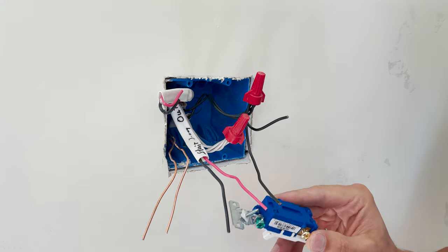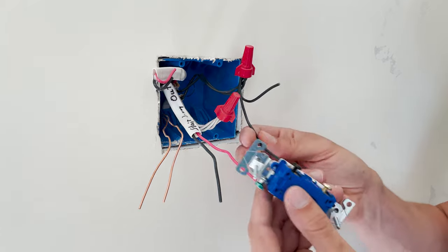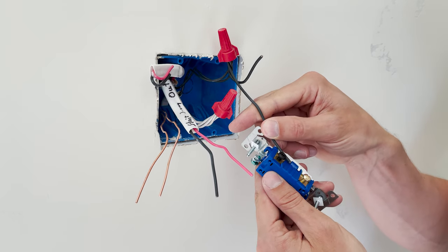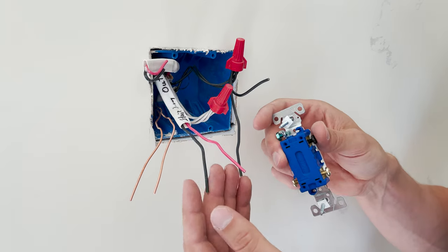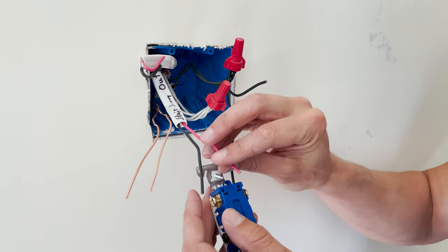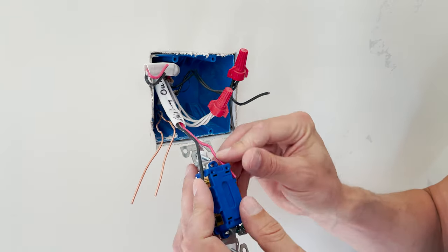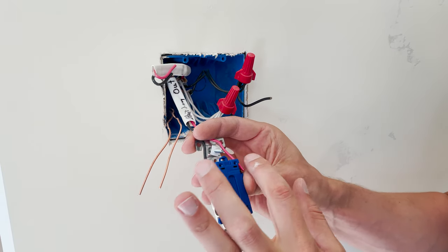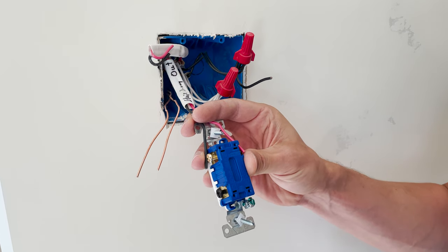So on this, we are going to ignore this kitchen one because we're not worried about that right now. We are going to connect the green to ground like normal. We will have this incoming power connected to this incoming wire, which is where the power is coming in. And then we will take our two outs to the other box with a three-way switch, and we will connect these like this, so that when we're switching, we will be switching between connecting this wire to this or this wire to this, and making it so that we have that functionality that we just discussed.